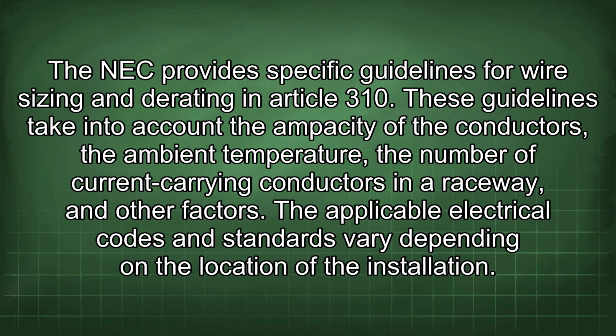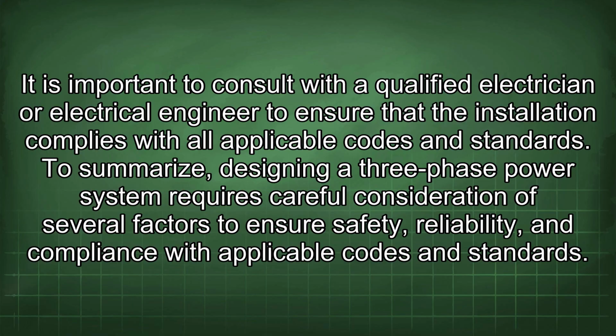The NEC provides specific guidelines for wire sizing and derating in Article 310. These guidelines take into account the ampacity of the conductors, the ambient temperature, the number of current-carrying conductors in a raceway, and other factors. The applicable electrical codes and standards vary depending on the location of the installation. It is important to consult with a qualified electrician or electrical engineer to ensure that the installation complies with all applicable codes and standards. To summarize, designing a three-phase power system requires careful consideration of several factors to ensure safety, reliability, and compliance with applicable codes and standards.